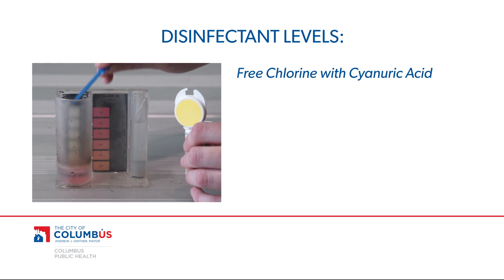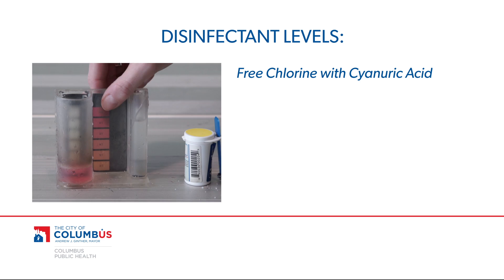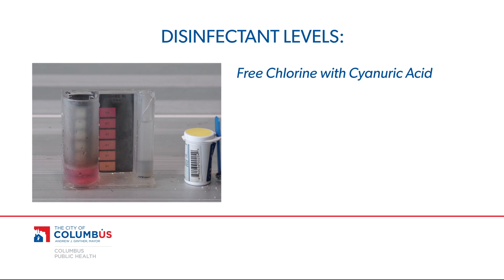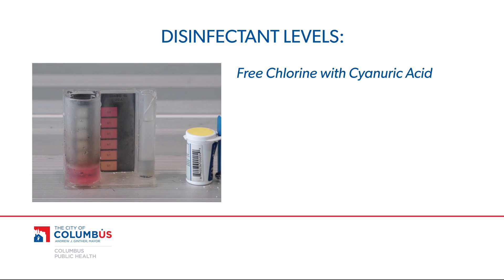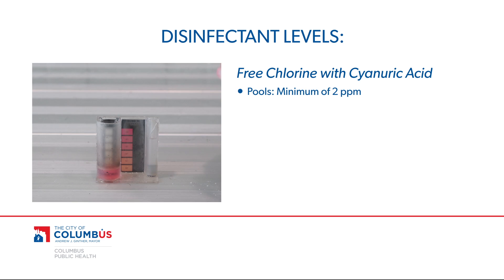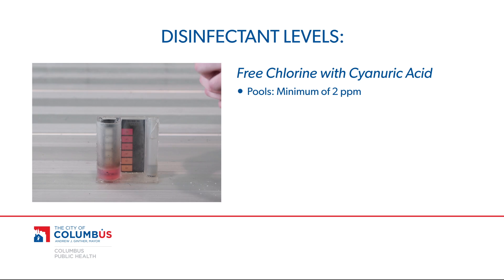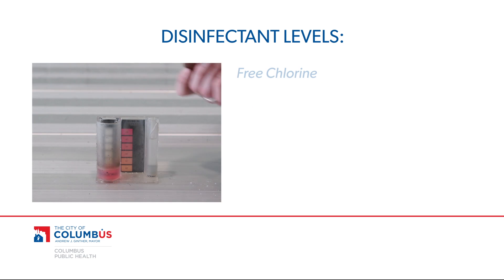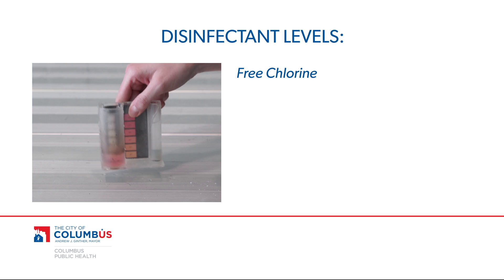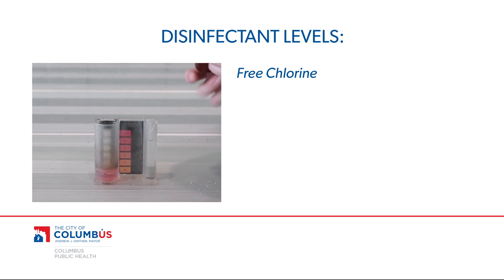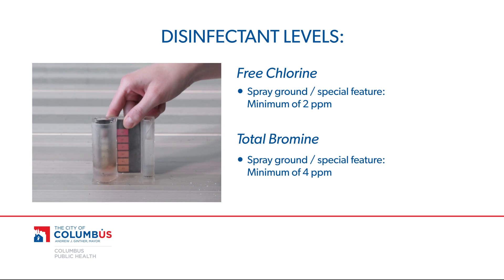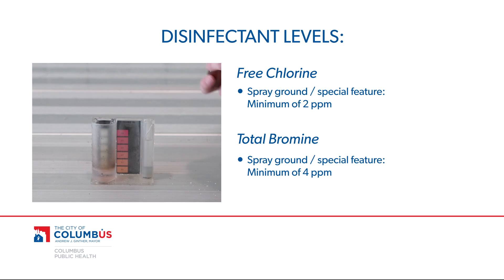If you use a chlorine product with cyanuric acid or add it as a supplement, then the disinfectant level must be higher, with free chlorine at 2 ppm in a pool and 3 ppm in a spa. Spray grounds and special features must maintain a free chlorine level of 2 ppm or 4 ppm bromine as measured from the spray orifice.